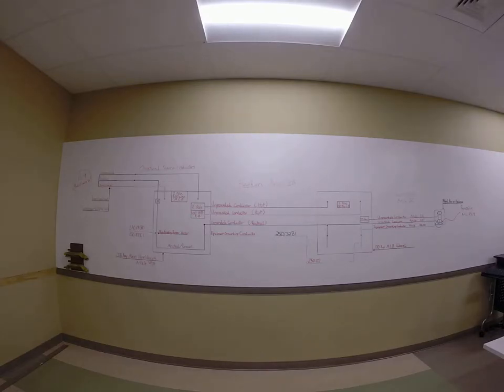All right, guys. This lesson is really trying to cover why we are required to have no main bonding jumper at a sub-panel. And oftentimes people install panels and they find a green screw in the box, and then they install the green screw, which connects the grounded circuit conductor to the equipment grounding conductor, or the metal box in the frame of the enclosure. And they do it by accident because they really don't know the theoretic danger that is inherent to doing that.